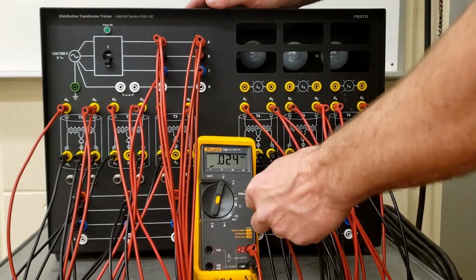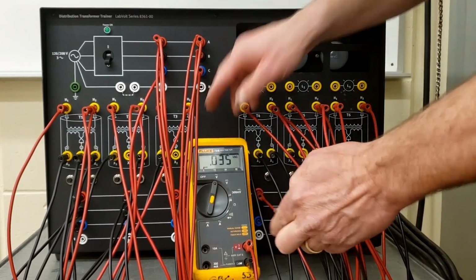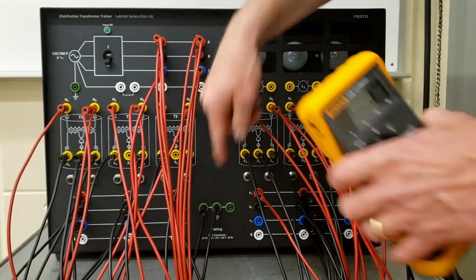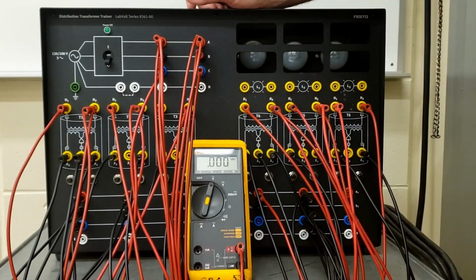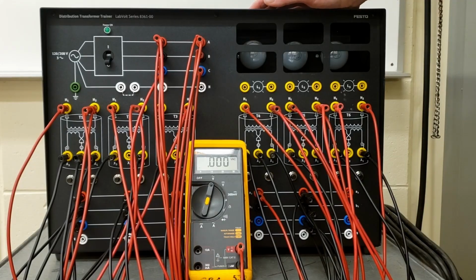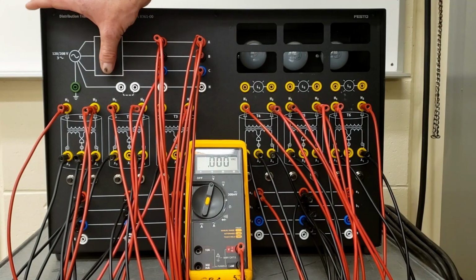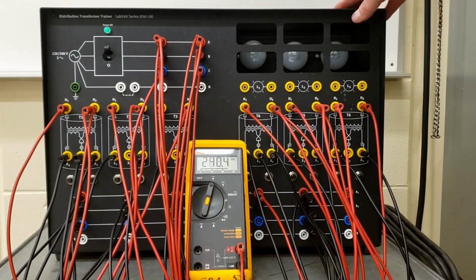So between these two buses, we've got to go between A2 and B2. You may want to have the students keep these lines open, so you can leave your meter in the center and just quickly check those. Before we saw 0 degrees phase shift with 0 volts between those - they were the same potential difference. Now we've got 240 volts between those.